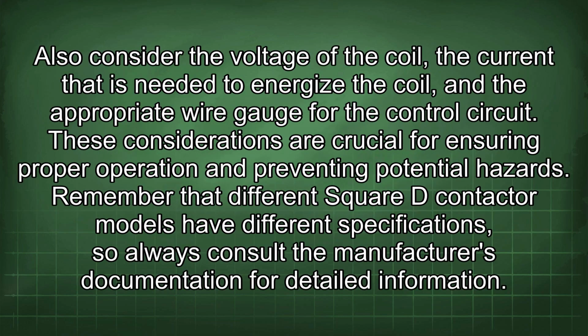Also consider the voltage of the coil, the current that is needed to energize the coil, and the appropriate wire gauge for the control circuit. These considerations are crucial for ensuring proper operation and preventing potential hazards. Remember that different Square D contactor models have different specifications, so always consult the manufacturer's documentation for detailed information.